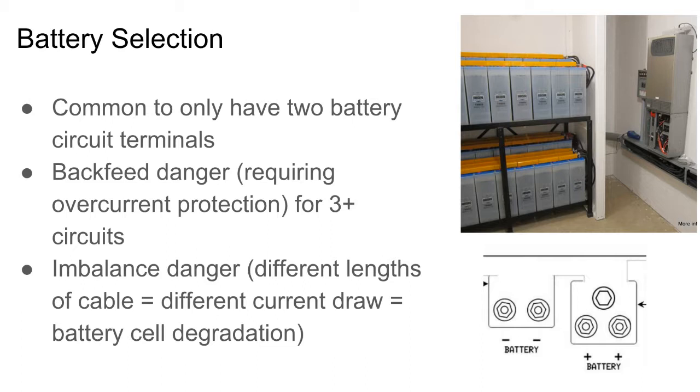Because if you backfeed the cable, it's rated for the backfeed. If you backfeed with 2 circuits into 1 circuit, then that circuit's not rated for the backfeed, and that's why the old-fashioned commercial string inverters would burn up. The circuits would ground fault, there's a blind spot in the ground fault detection, and it would cascade to where eventually you'd have 15 circuits faulting into one single number 10 PV cable. Got too hot, started burning holes in roofs.